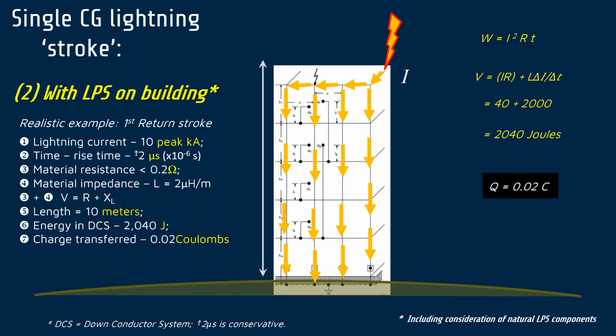And the matter of thatch roofs, where SANS 10313 says a minimum lightning protection level 3. As we tend to do as human beings, the documentation says minimum lightning protection level 3. Oh, good. So we will just put in lightning protection level 3. You arrive, you see a building, it's got thatch, it's lightning protection level 3. Ladies and gentlemen, that's not what it says. What it says is whatever you calculate. So before you look at it as being thatch, before you worry about whether or not it's going to burn because of lightning, before you do any of that, you do your assessments. And if you, in your assessments, find that you get a lightning protection level 4, you immediately change it to a lightning protection level 3.